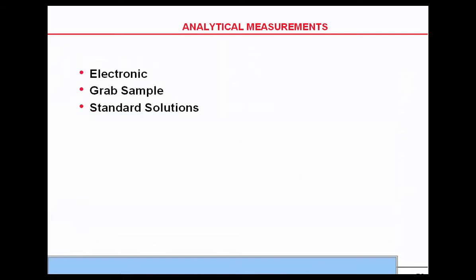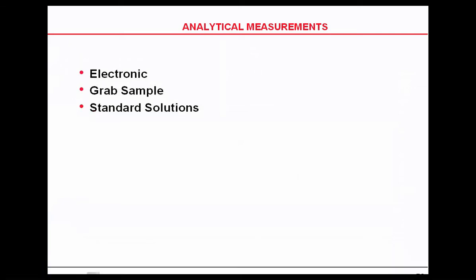Electronically, use a resistor for the grab sample. Use a standard solution of some known value. It's very difficult in a power plant to use something less than 10 or 15 microsiemens solution. The minute you open that cap, you contaminate it with CO2 and what's in the air, and that sample is no longer good to use. So you should use something higher than those very low bottles of conductivity solution.